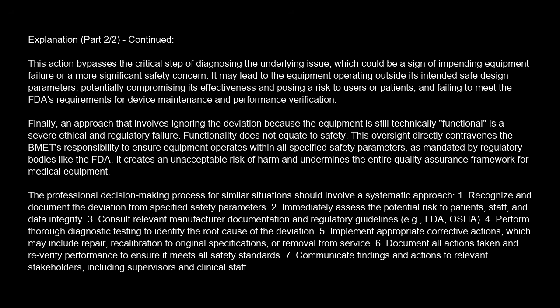1. Recognize and document the deviation from specified safety parameters. 2. Immediately assess the potential risk to patients, staff, and data integrity. 3. Consult relevant manufacturer documentation and regulatory guidelines, e.g., FDA, OSHA. 4. Perform thorough diagnostic testing to identify the root cause of the deviation. 5. Implement appropriate corrective actions, which may include repair, recalibration to original specifications, or removal from service. 6. Document all actions taken and re-verify performance to ensure it meets all safety standards. 7. Communicate findings and actions to relevant stakeholders, including supervisors and clinical staff.